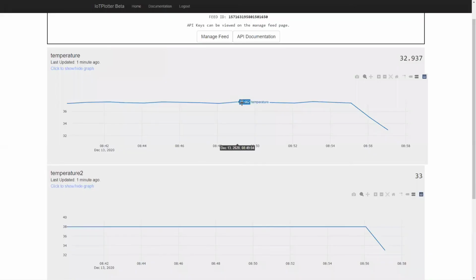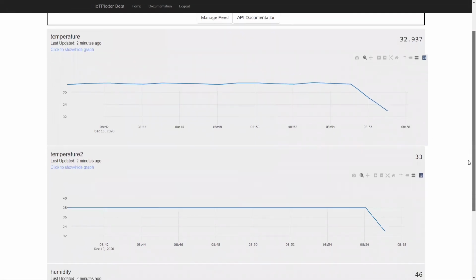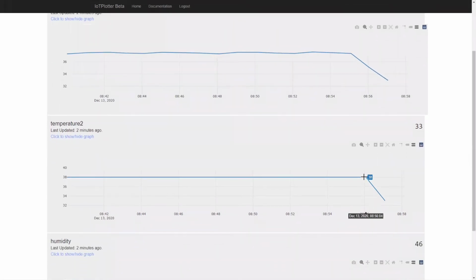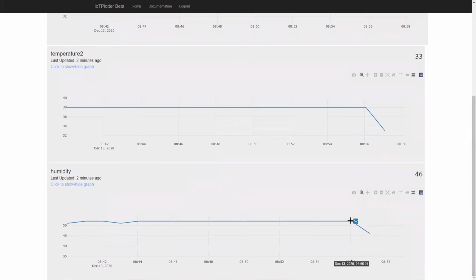Yeah, the temperature was steady at 37.5. We opened the incubator, and then you can see that the temperature abruptly dropped from 37 to 32. So it's a drop of 5 degrees immediately. This happened to both the temperature sensors, and then we can also see that the humidity abruptly dropped. There's a lot of water vapor content inside, but when we opened it, the water immediately left the incubator, and consequently the humidity dropped. That's also a significant drop, 52 to 46.